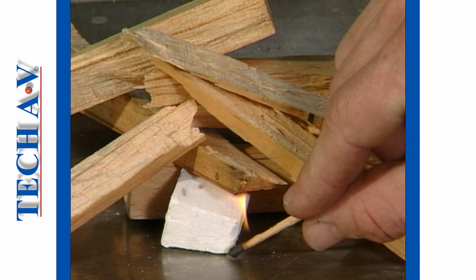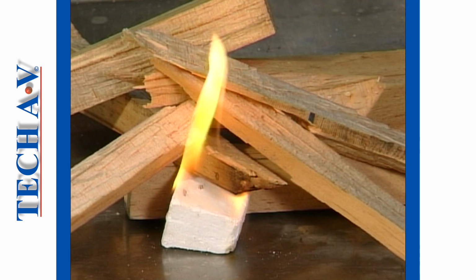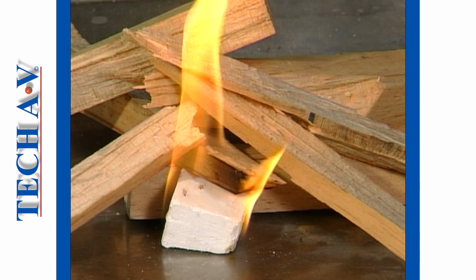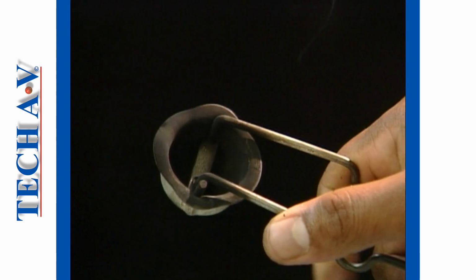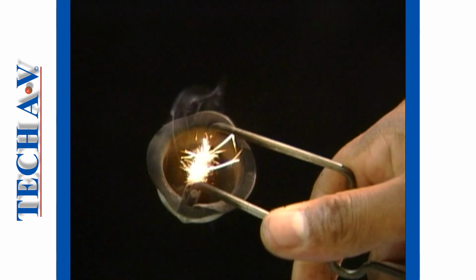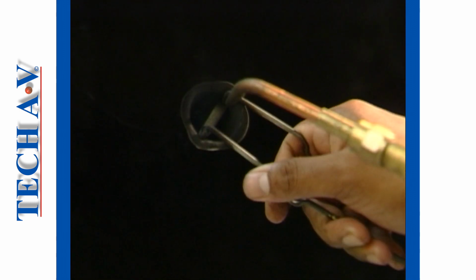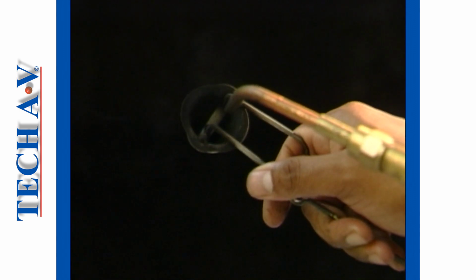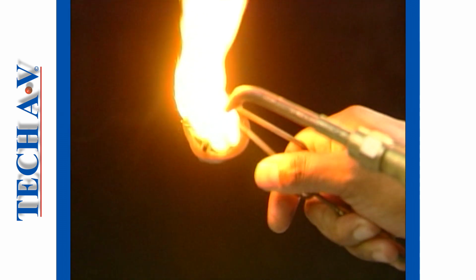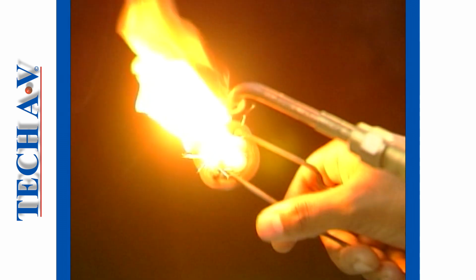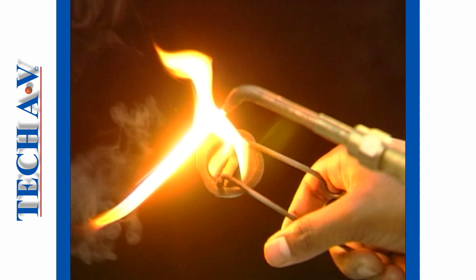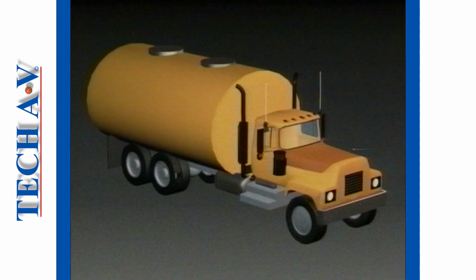Solids normally require a generous amount of heat in order to sustain the combustion process. However, a flammable gas or vapor requires only the heat generated from a spark, as demonstrated here with welding gas, that is to say, oxyacetylene. When flammable gases or vapors exist within the atmosphere of a confined space, the same little spark can set off an explosion.